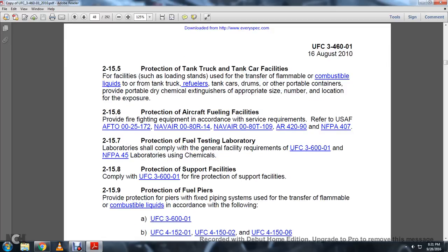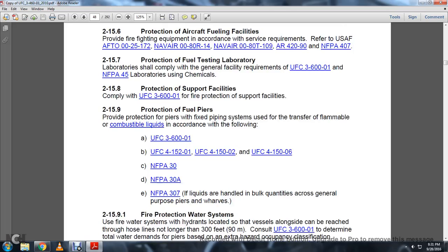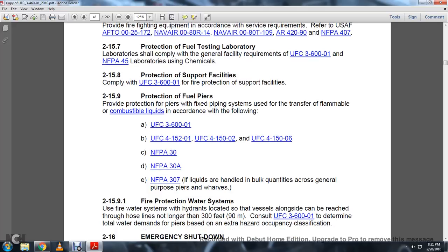Provide protection for the piers with fixed piping systems used for the transfer of flammable and combustible liquids in accordance with the following: UFC 3-600-01, UFC 4-152-01, UFC 4-150-02, UFC 4-150-06, and NFPA 30, 307 if the liquids are handled in bulk quantities across the general purpose piers and wharves.